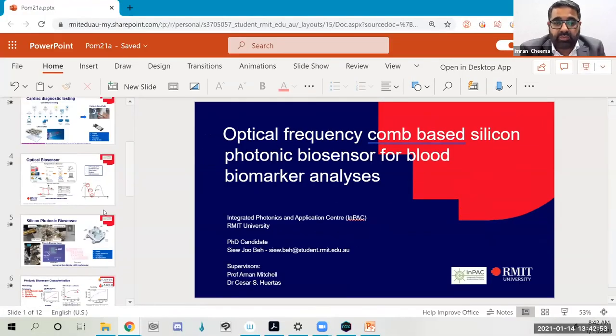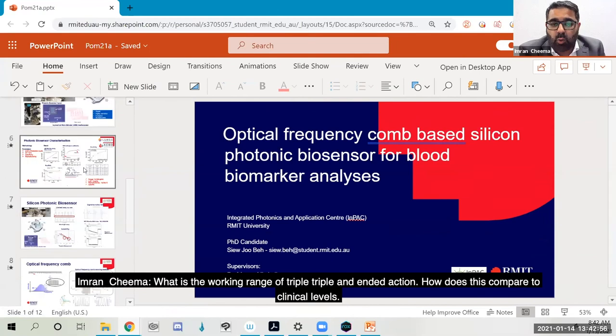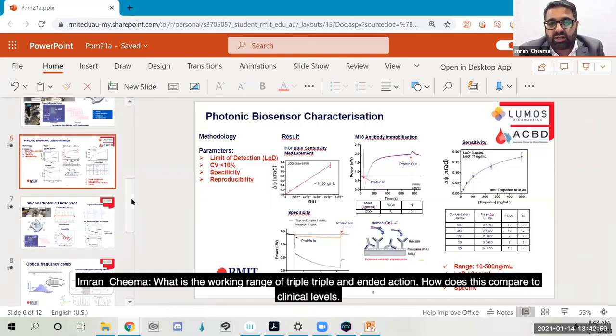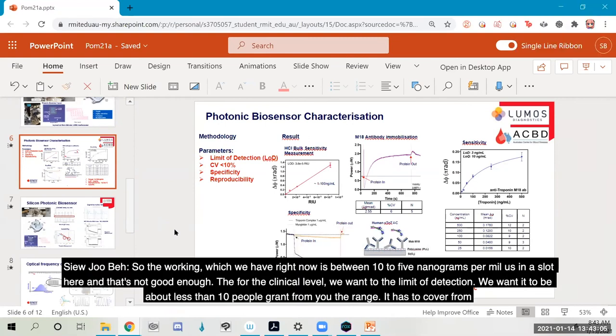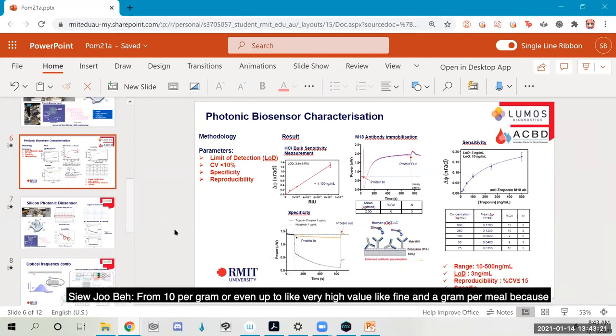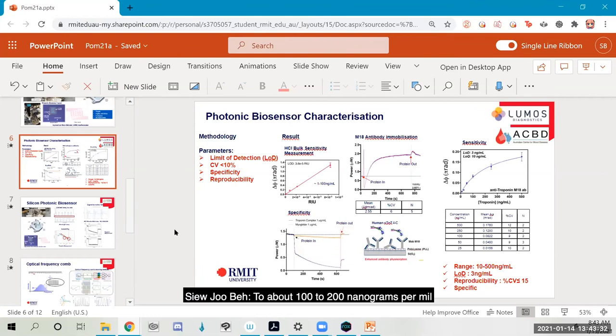What is the working range of troponin detection, and how does this compare to clinical levels? The working range we have right now is between 10 to 500 nanograms per mil, as shown in the slide, and that's not good enough. For the clinical level, we want the limit of detection to be less than 10 picograms per mil. The range has to cover from 10 picograms or even lower up to very high values like 500 nanograms per mil, because when somebody suffers a heart attack, troponin levels go up to about 100 to 200 nanograms per mil.